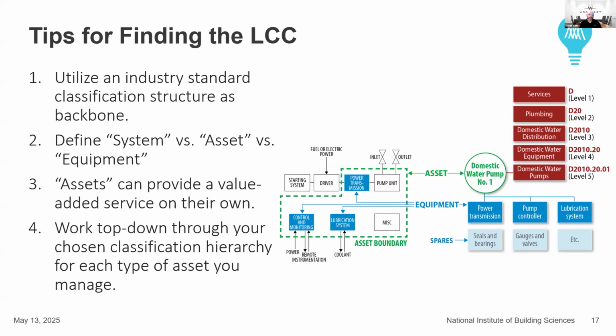So again, using the example of the enterprise asset management system, it can have the transmission, the pump controller, the lubrication system as individual assets, so long as it also has the relationship to the specific domestic water pump assembly they're a part of. Conversely, the financial system might aggregate all the water pumps and other water distribution system components installed as part of a discrete project and track the book value of that system as a whole. In this method, it's okay as long as the system maintains a relationship to all of the individual LCC assets it's comprised of.